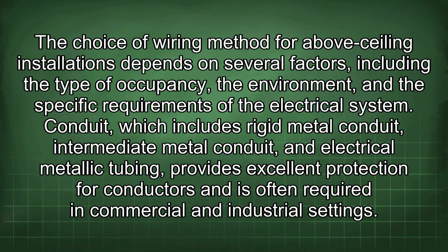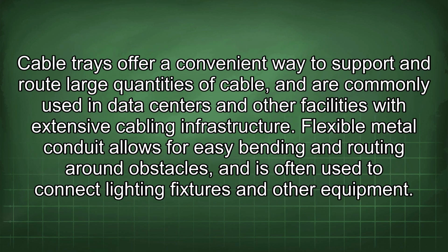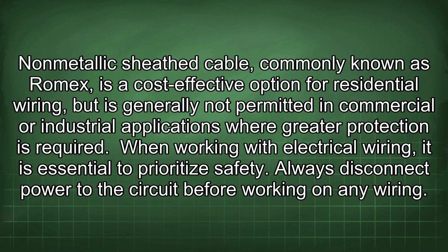Conduit, which includes rigid metal conduit, intermediate metal conduit, and electrical metallic tubing, provides excellent protection for conductors and is often required in commercial and industrial settings. Cable trays offer a convenient way to support and route large quantities of cable, and are commonly used in data centers and other facilities with extensive cabling infrastructure. Flexible metal conduit allows for easy bending and routing around obstacles, and is often used to connect lighting fixtures and other equipment. Non-metallic sheathed cable, commonly known as Romex, is a cost-effective option for residential wiring, but is generally not permitted in commercial or industrial applications where greater protection is required.